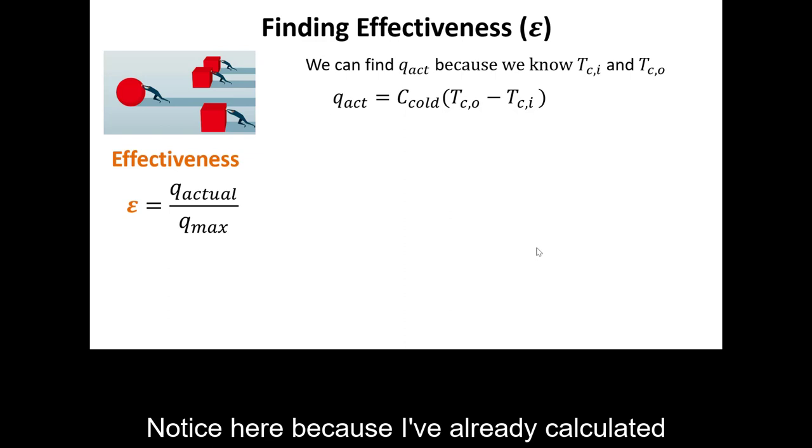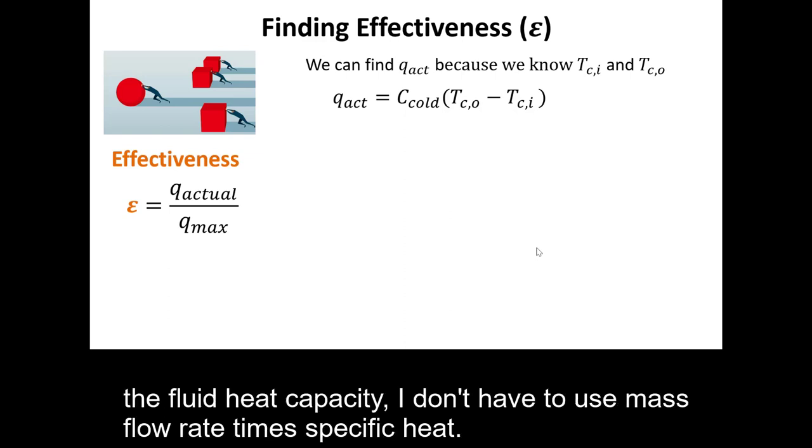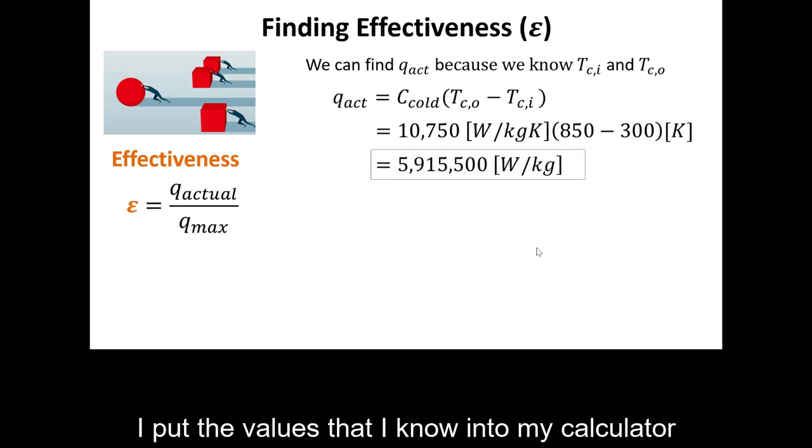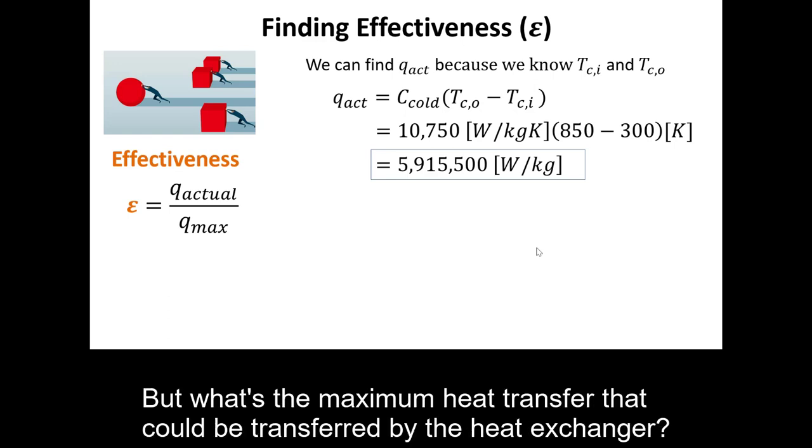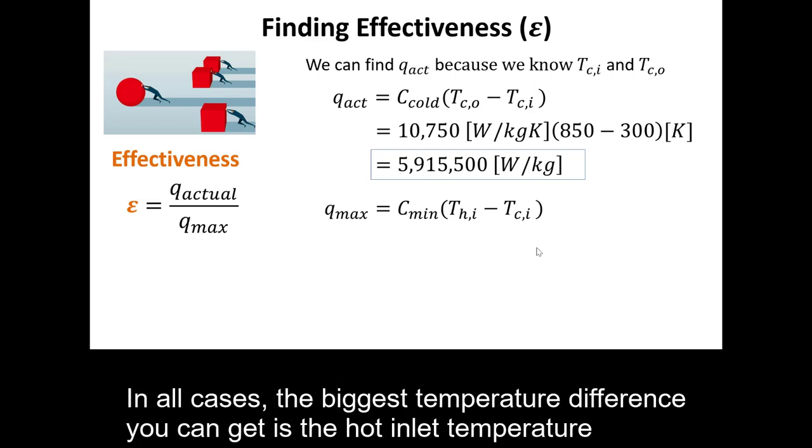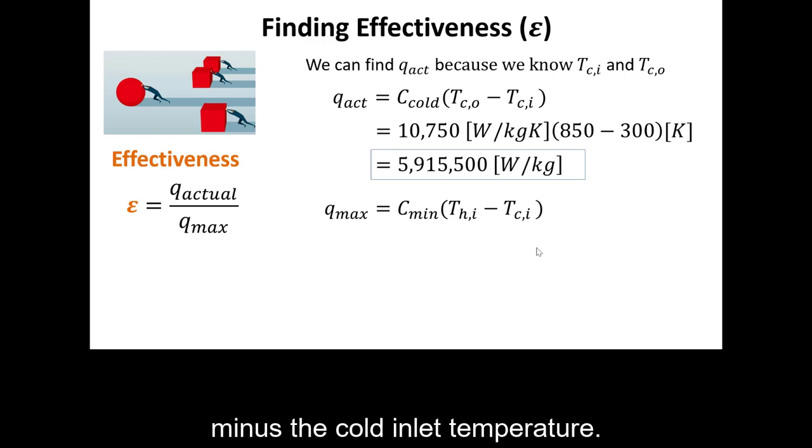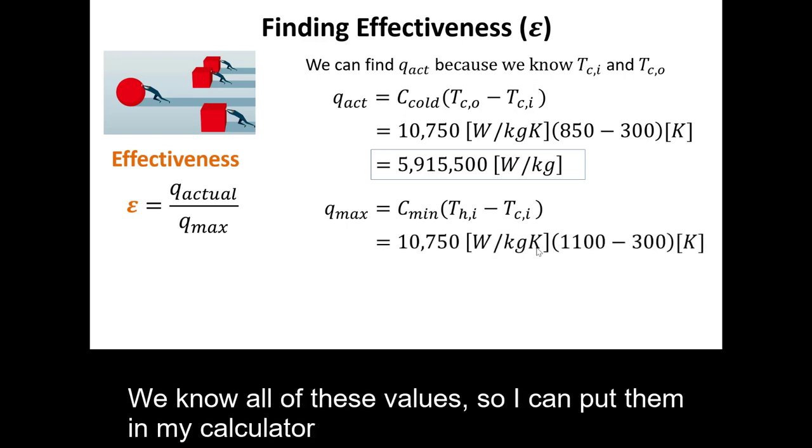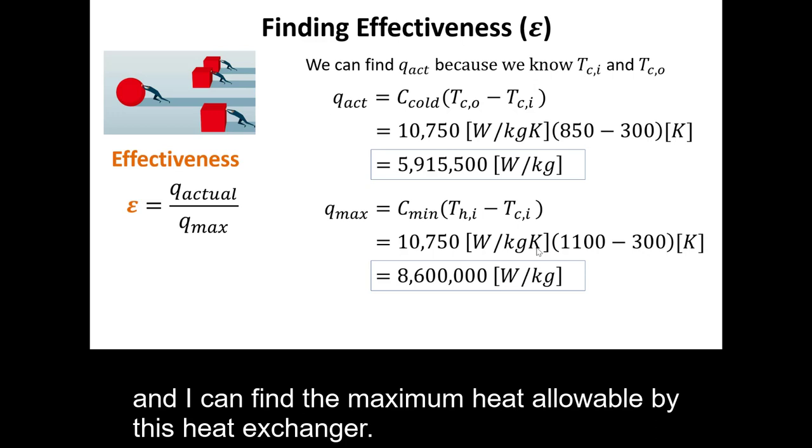Notice here, because I've already calculated the fluid heat capacity, I don't have to use M dot times C P. I put the values that I know into my calculator and I find how much heat is actually transferred by my heat exchanger. But what's the maximum heat transfer that could be transferred by the heat exchanger? In the maximum case, we take the minimum fluid heat capacity and multiply by the biggest temperature difference we can get. In all cases, the biggest temperature difference you can get is the hot inlet temperature minus the cold inlet temperature. We know all of these values, so I can put them in my calculator and I can find the maximum heat allowable by this heat exchanger.